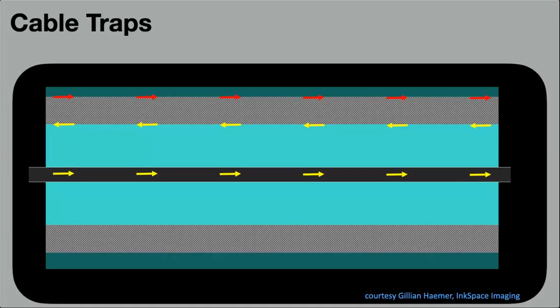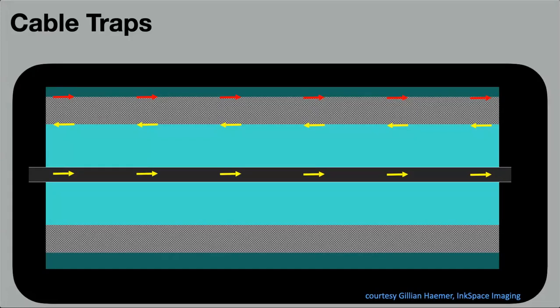These are parasitic so-called common mode currents that can easily freely flow there. That is a real issue, because effectively whenever you have a conductor, this is the signal, and that's fine, but the outside of the shield, that's where the trouble is. That can interact with the transmitter.